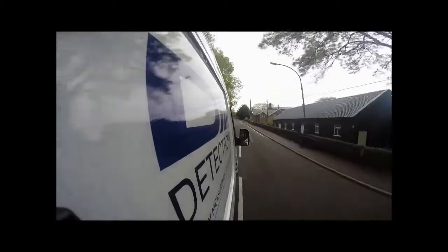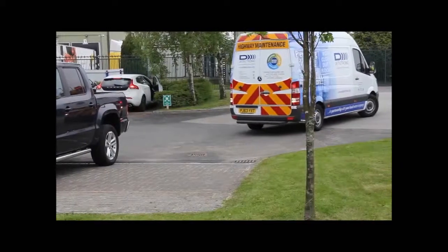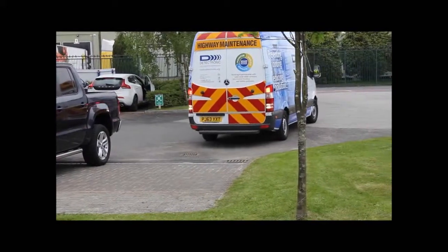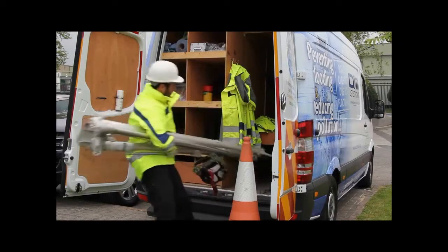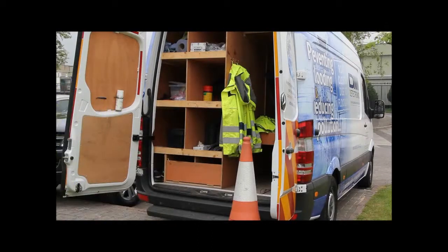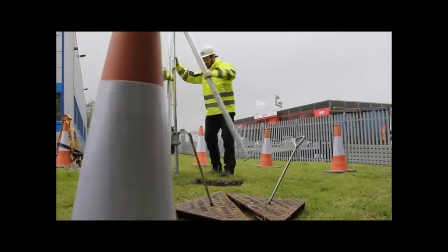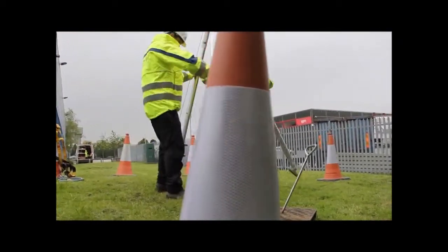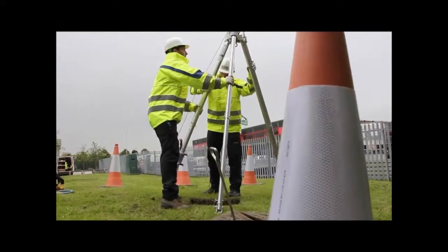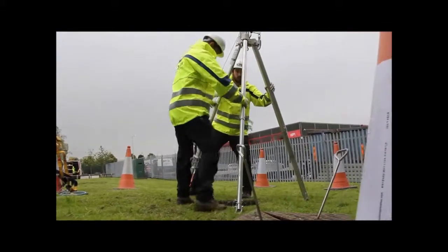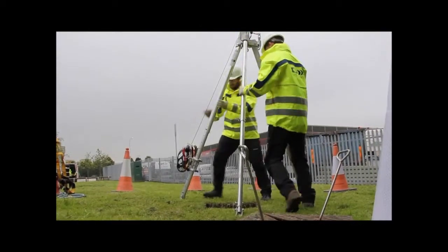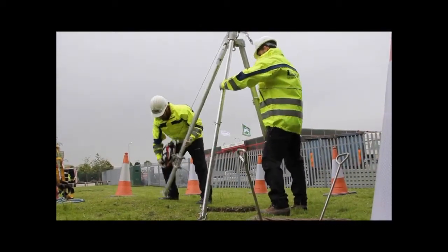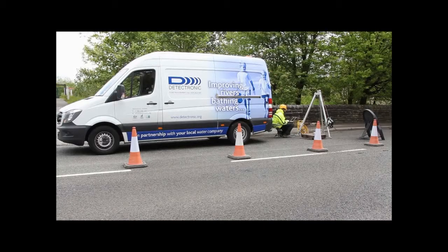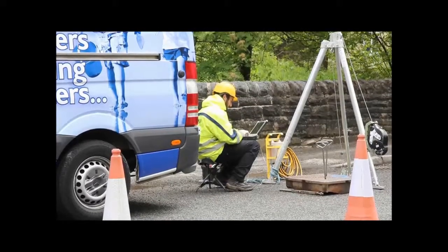Installation for our flow meter and ultrasonic level monitor is carried out by Detectronic's skilled 2 or 3 man teams. When arriving on site, the crew will make sure that the work area is safe, when necessary setting up safety barriers and cones. The safety harness and recovery rig is set up for the person entering the sewer. These safety precautions are taken whether working in an enclosed area or on a public footpath or road.